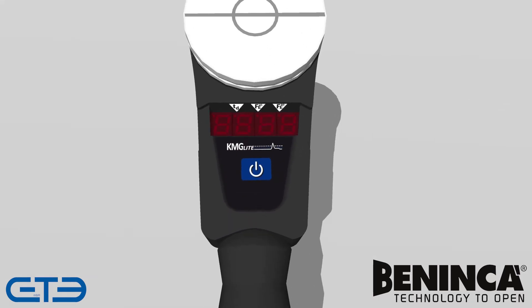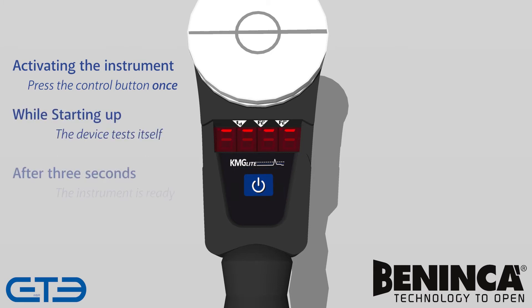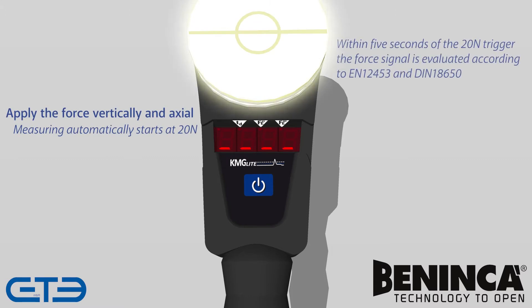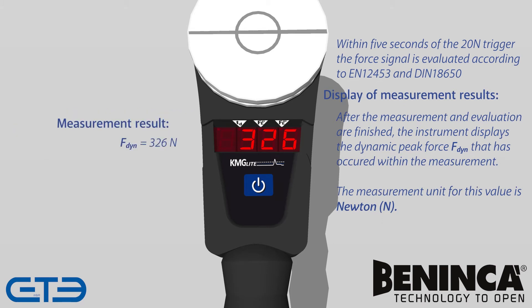Activating the instrument: press the control button once. While starting up, the device tests itself. After three seconds, the device is ready. When ready, apply the force vertically and axially — measuring will automatically begin at 20 N. Within five seconds of the 20 N trigger, the force signal is evaluated according to EN 12453 and DIN 18650. After measurement and evaluation are finished, the instrument automatically displays the dynamic peak force. The measurement unit is in N; here we have a dynamic peak force of 326 N.